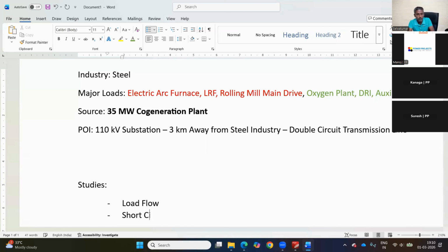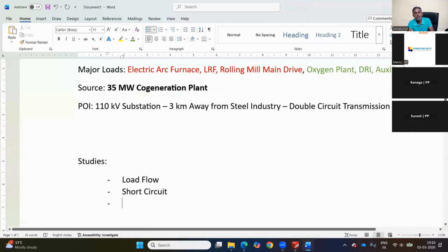You need to perform a short circuit study to find out the short time rating of equipment, the breaking, making, and DC interrupting capabilities of equipment, and to find out the voltage rise during unbalanced faults in resistance grounded systems. You need to perform short circuit.